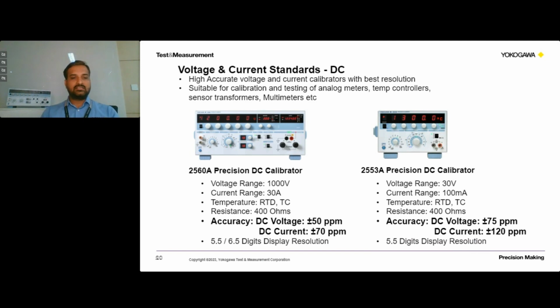If you see both the 2560 and 2553A, the 2553A is a must-have product if you are looking at lower voltage and lower current applications, such as process calibration of process indicators, process panel parameters, and panel meters installed in the process industry, those kinds of DUTs. Whereas the 2560A is a must-have product if you are working on higher range DC current and DC voltage applications, since it has a wide voltage range as well as a current range up to 30 amps.